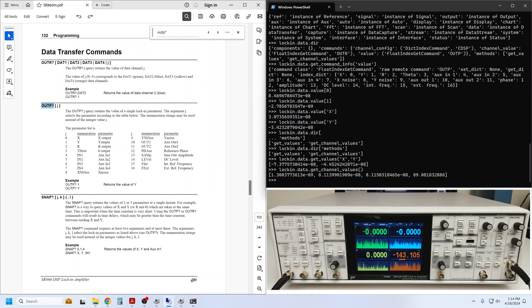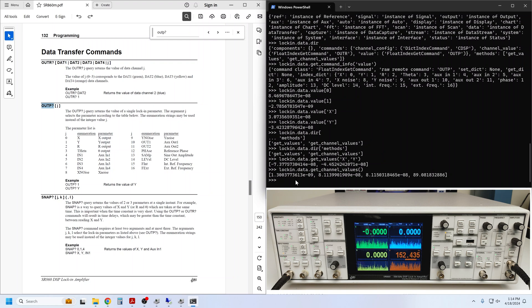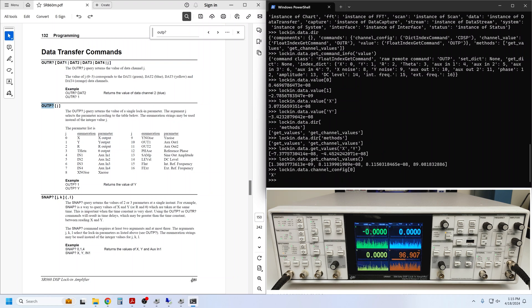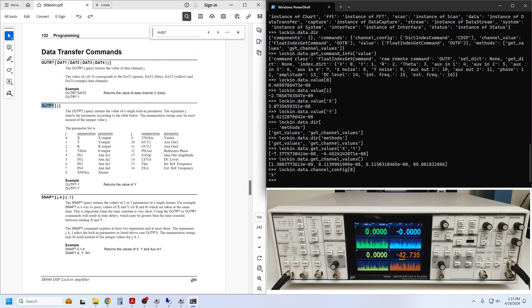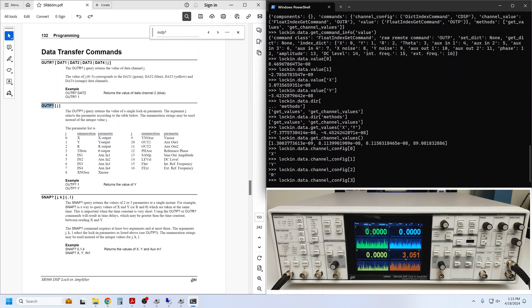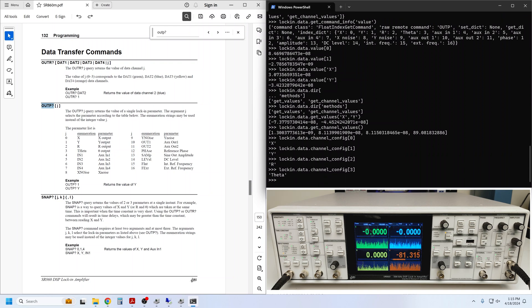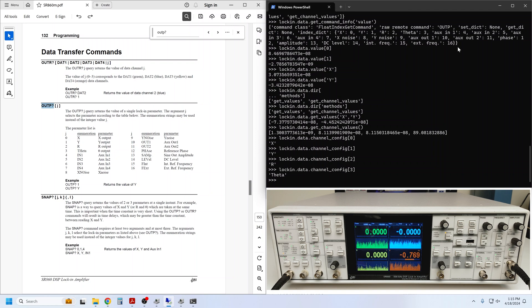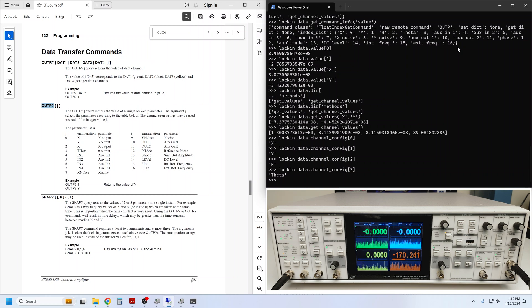We can use the channel_config command to query or set the parameters that are mapped to those four channels. So, if I want to know what's on channel 0, I can ask this. We see that x is mapped to channel 0, just like we see on the front panel. y is on channel 1, r is on channel 2, and theta is on channel 3. These can be configured using the same strings or indices used with the data.value command above. For most of this tutorial, I'll use the get_values_xy command to capture x and y simultaneously.